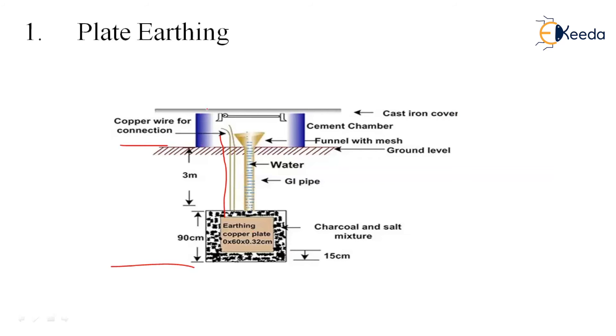A cast iron cover is kept over the pit. The standard procedure is: dig to a minimum of 3 meters deep, place a copper plate or galvanized plate — dimensions vary depending on the type of plate. Fill with charcoal and salt mixture. The lower layer of mixture should be present first, then the copper plate, then the complete mixture again. Providing a funnel is better to keep moisture intact throughout, especially in the summers. This was the plate earthing.